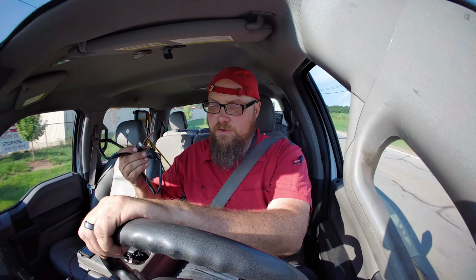So in this particular case, I was checking between the black and the red, because on these particular units, you want to see about 4.5 to 5 volts DC there. If you do not see that, then you probably have an issue with your board itself and not a transducer issue. Then we saw that was okay, being 4.97, I think it was. So we moved along to the black and the white, which is telling us what the actual resistance or the voltage coming through the resistor in here is. So we were seeing, I think it was 0.033, which is below the 0 set point on that. I think 0 is 0.05 on that guy.